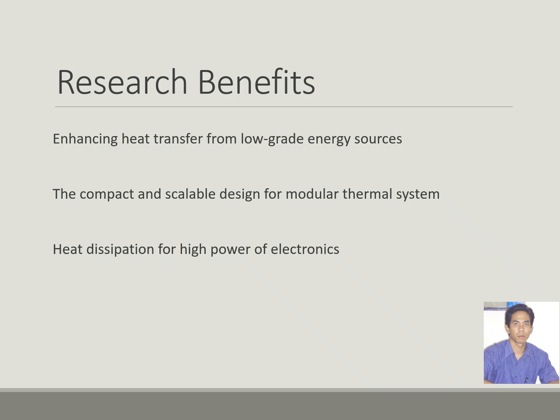In the context of modern high-power electronics such as processors, GPUs, power electronics, and high-frequency communication devices, thermal management has become a critical challenge. Elevated operating temperature significantly accelerates material degradation and increases the risk of component failure. The implementation of a micro heat exchanger can effectively reduce the overall thermal resistance of the system, mitigate localized overheating or hotspots, and maintain more stable operating temperature. Moreover, precise temperature control enhances system reliability and significantly extends the operational lifespan of electronic components.